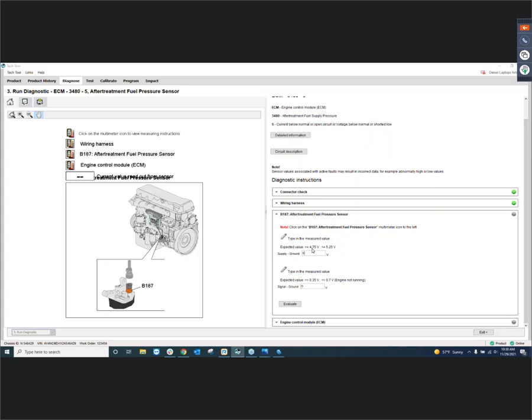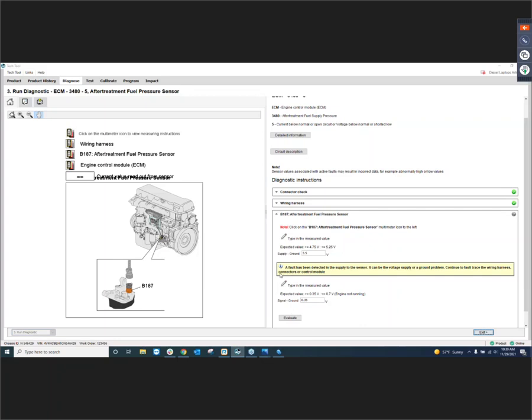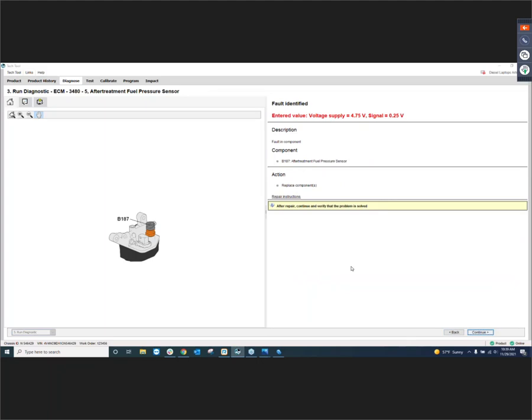How many volts did you see? The expected value is between 4.75 and 5.25 volts. So here I'm going to put 3.5 volts, and on the ground circuit I'll just put the expected value. Now you take those measurements, put the numbers in, and click evaluate. It tells you where the problem is - the problem detected by the sensor can be the voltage supply or the ground - continue fault tracing. Then you can go back and change this any which way - say 5, and change this one to something else. Hit evaluate again - it says you have good 5, nothing coming out, and it's going to tell you to replace that sensor.